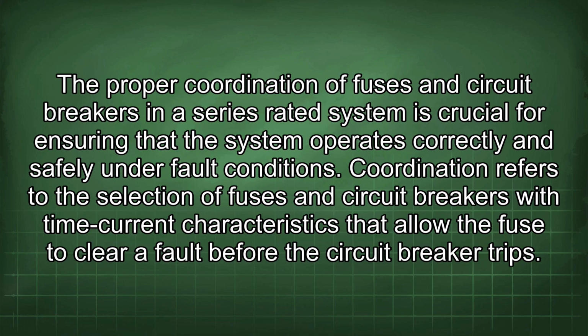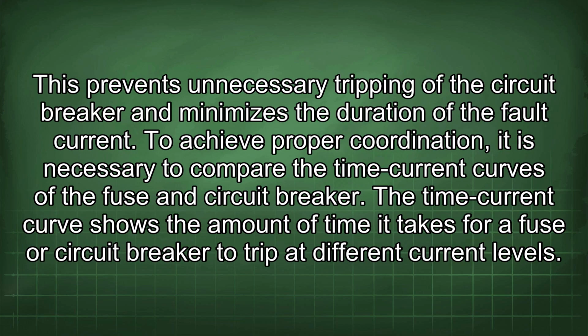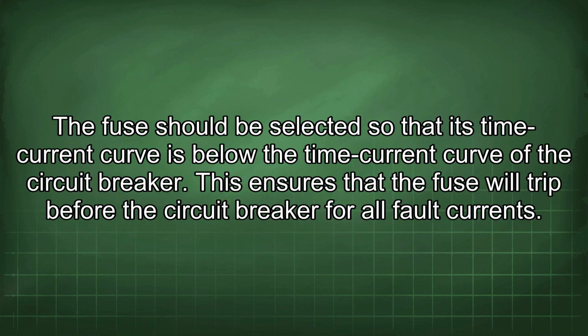Coordination refers to the selection of fuses and circuit breakers with time current characteristics that allow the fuse to clear a fault before the circuit breaker trips. This prevents unnecessary tripping of the circuit breaker and minimizes the duration of the fault current. To achieve proper coordination, it is necessary to compare the time current curves of the fuse and circuit breaker. The time current curve shows the amount of time it takes for a fuse or circuit breaker to trip at different current levels. The fuse should be selected so that its time current curve is below the time current curve of the circuit breaker. This ensures that the fuse will trip before the circuit breaker for all fault currents.